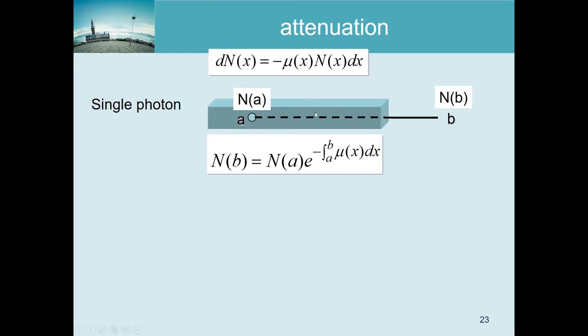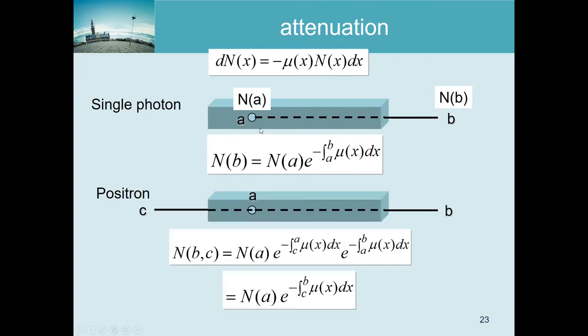The attenuation coefficient may depend on position if the material is not uniform. This is the same differential relation we saw for radioactivity, and the solution is the same: an exponential. Because mu(x) is not constant but depends on position, we get an integral in the exponent. The number of photons arriving at detector B equals the number that started at A, reduced by the exponential of the total integrated attenuation along the line.